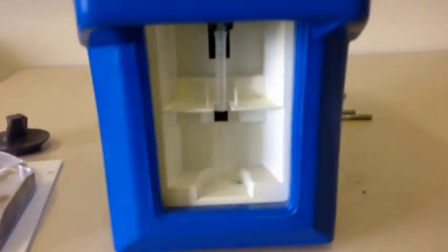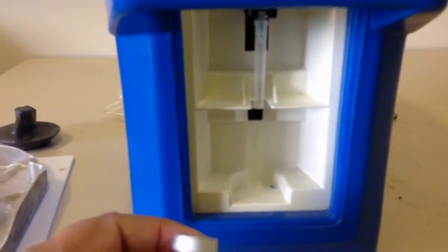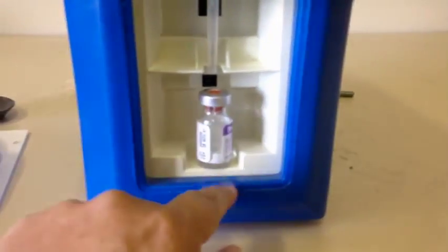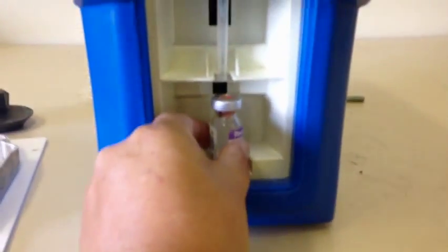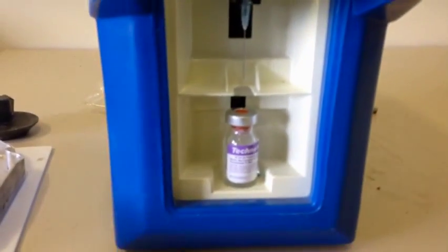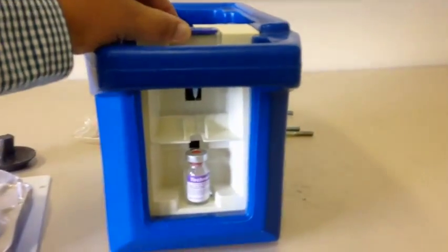The outside of this comes into this mechanism that I'm about to pull out. Before I pull it out, it's the housing where we have our needle and elution pot. I don't have an elution pot for this because it's such an old system—these have been out of date for quite a few years. But you would have a lead pot with an evacuated vial that would sit in here. Obviously you would remove the needle—I won't use the lead pot because you won't be able to see what's going on.